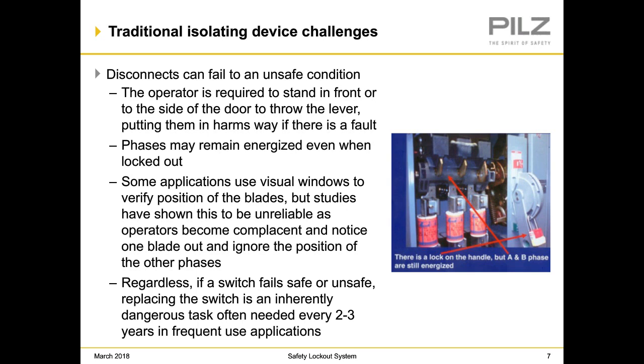And this probably happened to other people. It happened to me recently in an email I read. I missed a word in the email and it totally changed the meaning of the email. So it's subconscious, but it can happen. Again, studies have shown that that is not necessarily a reliable method of verifying that the switch operated properly. Regardless, if a switch fails, safe or unsafe, replacing the switch is an inherently dangerous task and often needs to be done every 2 to 3 years in frequent use applications.